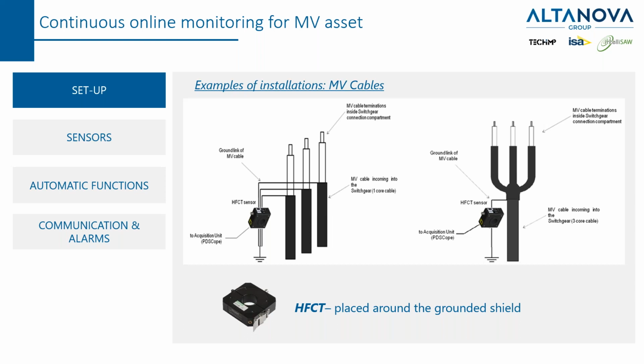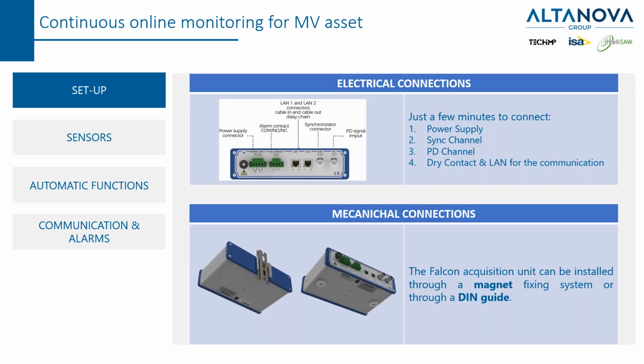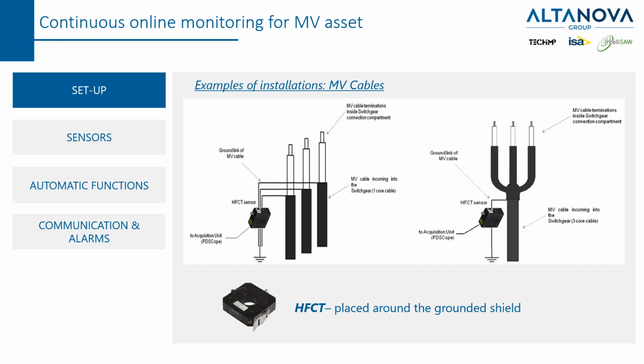If we want to compare, sorry if I go back, if we want to compare the installation of the Falcon unit with the IntelliSAW that I mentioned before, it is important to note that this Falcon unit is not intrusive and is designed to detect the partial discharge rather than the humidity, and it is installed outside the compartment of the switchgear. In fact, the typical example of installation of the sensor in this slide we are mentioning, the HFCT, that is the high frequency current transformer.